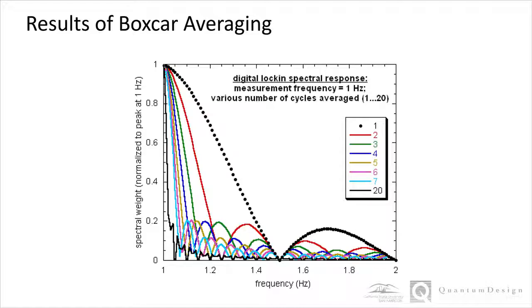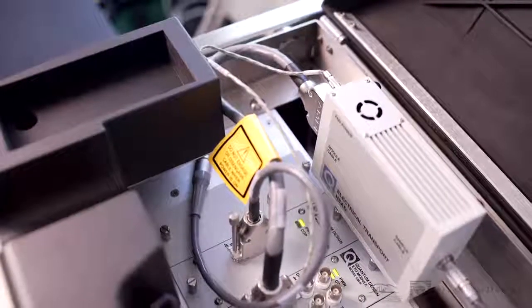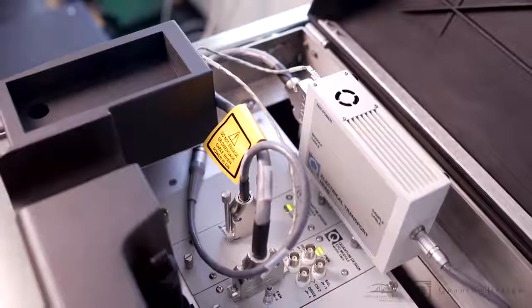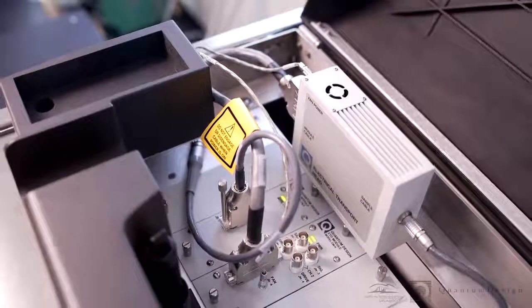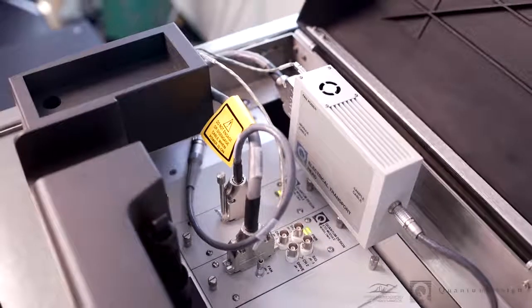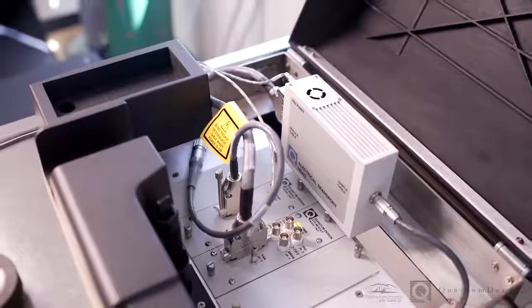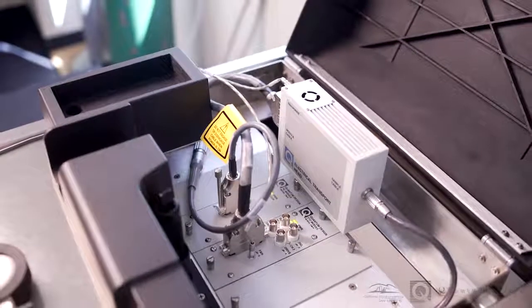The ETO possesses two measurement channels with their own dedicated electronics, meaning that two sets of precision current sources and voltmeters are individually running at all times. The current source's maximum output is 100 milliamps with 1 nanoamp minimum precision, and the output modes include DC or AC, with a frequency range between 0.1 Hz to 200 Hz.